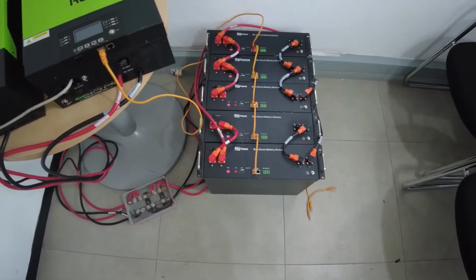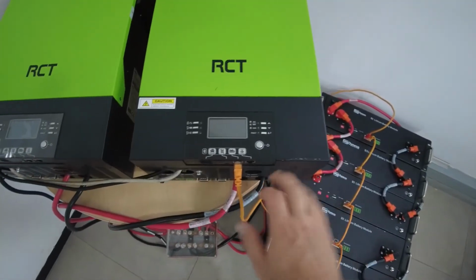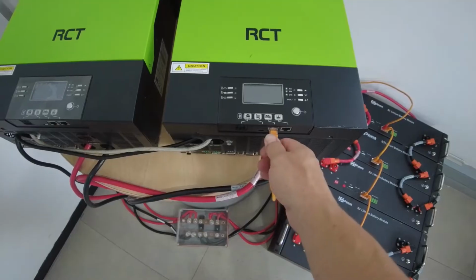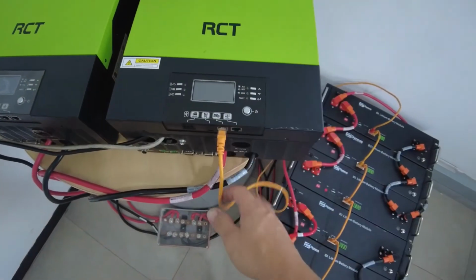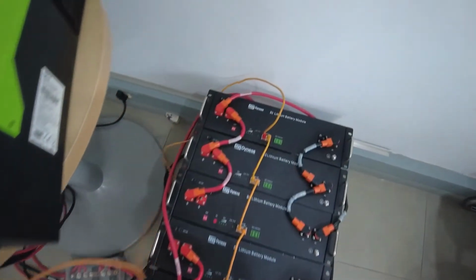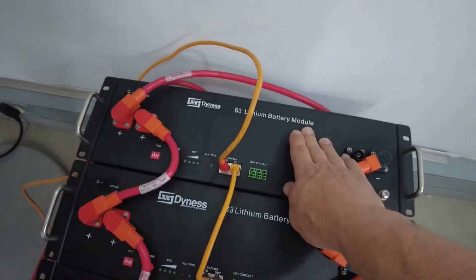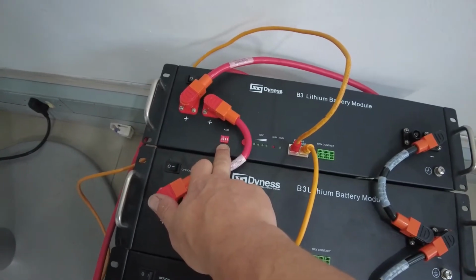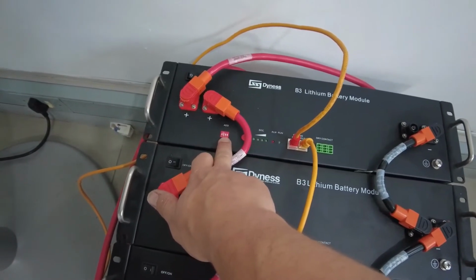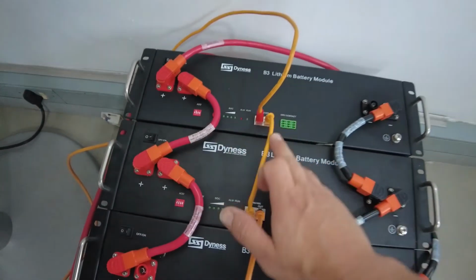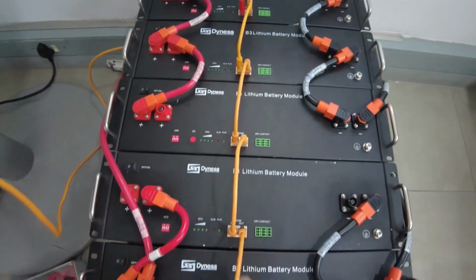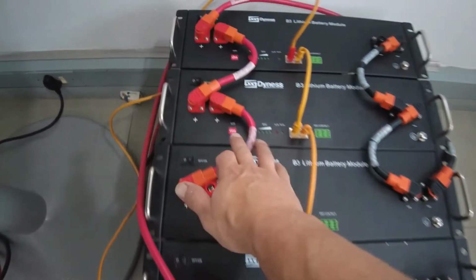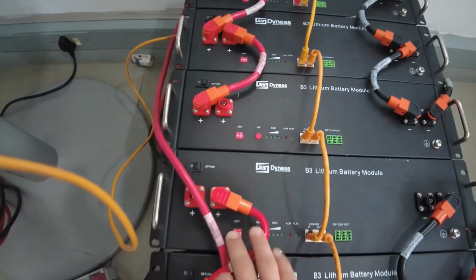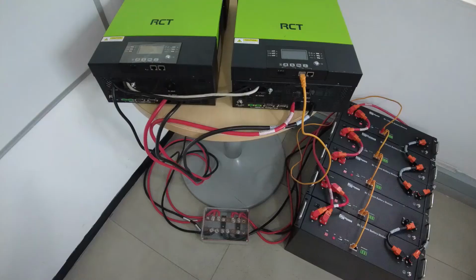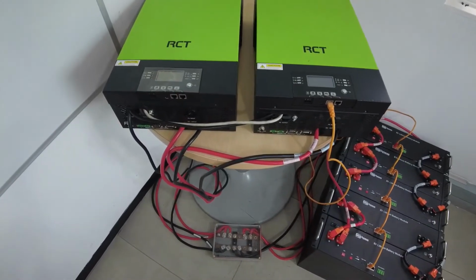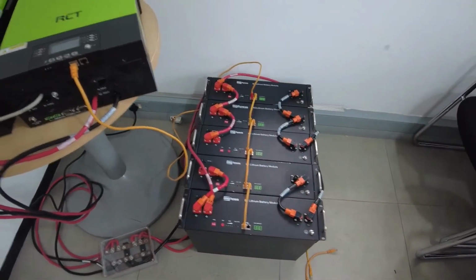Okay, so just to recap, the inverter using the networking cable, the BMS cable that we've rewired, will be the inverter communicating with the battery. This will run to the first battery module that we've set as a master, dip setting 0, 1, 0, 0. From there you run out to in, out to in, out to in on all of your batteries, with your dip settings all on 0, 0, 0, 0. Okay, so the wiring between the inverters and the batteries is currently done.